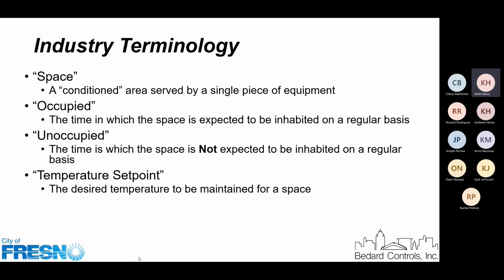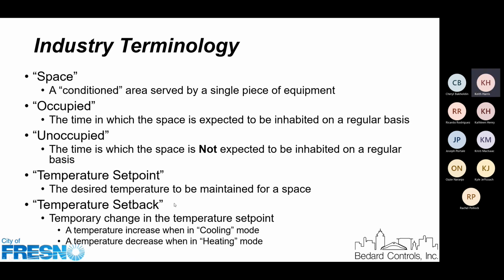So we have a temperature that we want to maintain when we think people or occupants are in the space. Then we have a setback that is a temperature either higher in cooling or lower in heating that we allow the space to drift to when we expect no one to be occupying that space. So we'll talk about set points and we'll talk about setbacks, and the two are used in regards to the unoccupied and the occupied times.